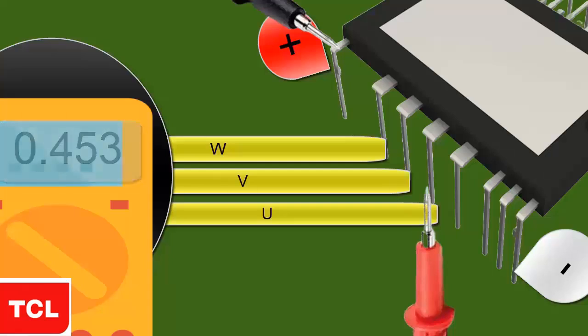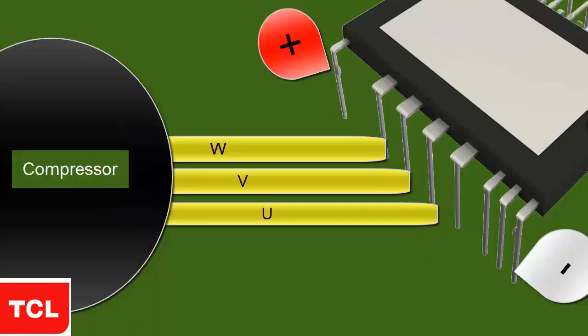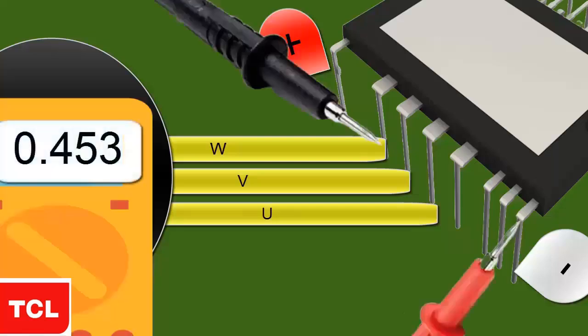Let's proceed with the integrity test of the last three diodes. Place the red probe of the multimeter on the negative input of the IPM electronic circuit. Use the black probe to measure the points UVW.